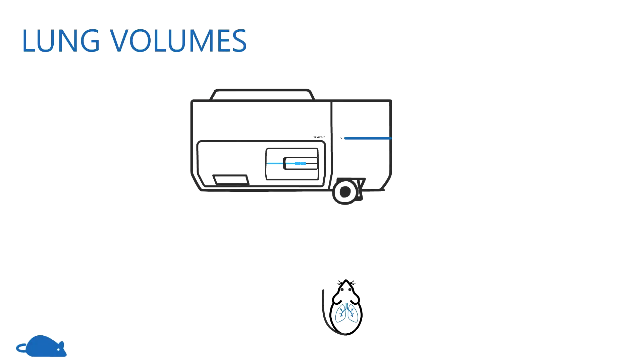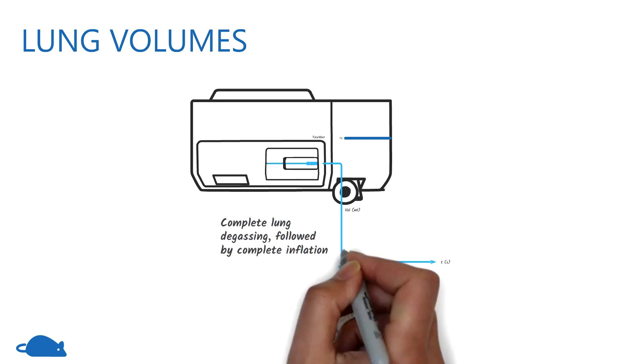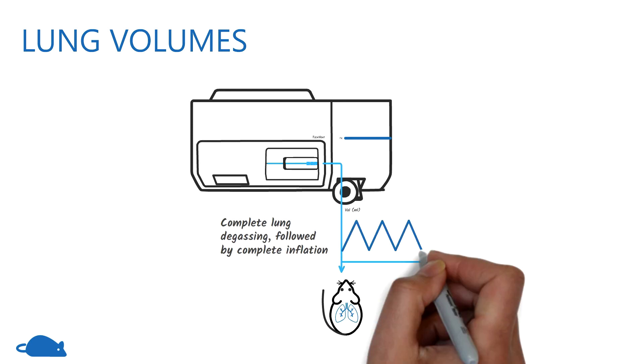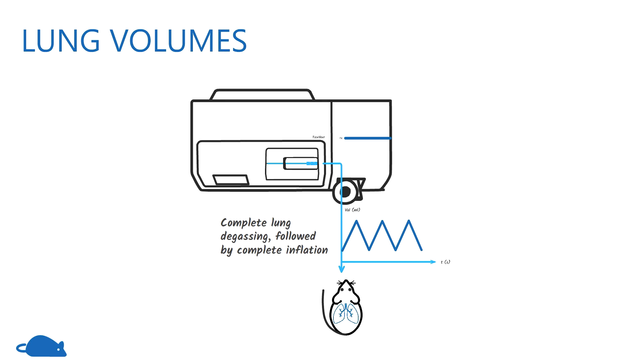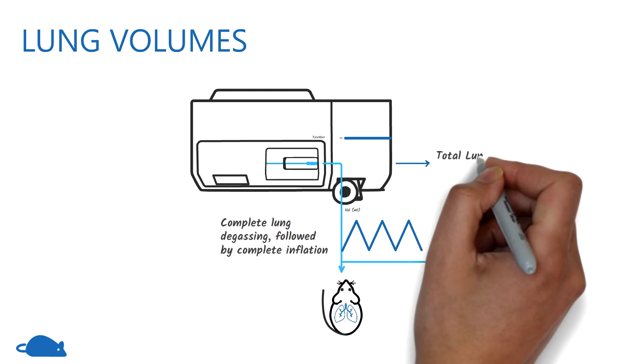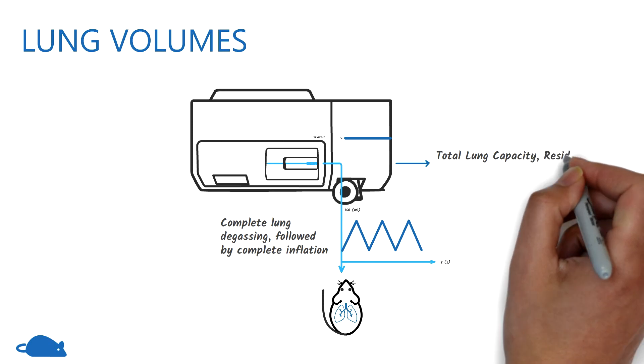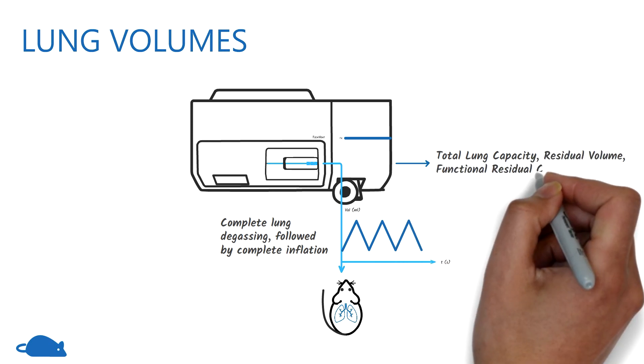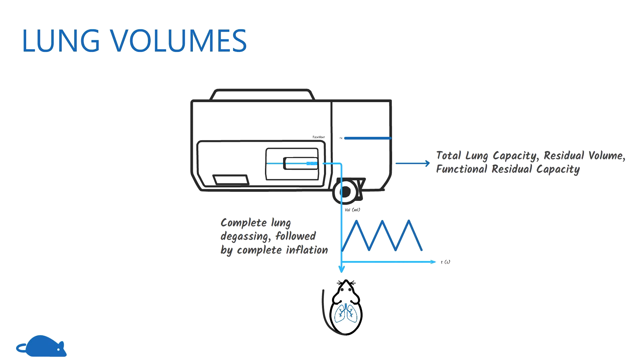In the lung volumes measurement, the lungs are completely degassed after ventilating with pure oxygen and then re-inflated back to total lung capacity. The flexiVent then calculates the total lung capacity, residual volume, and functional residual capacity.